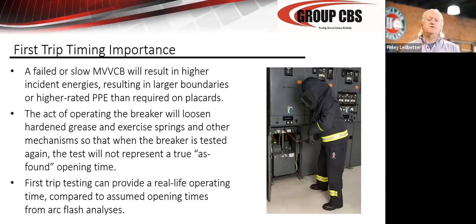Gathering that first trip information is critical to understand whether or not your breaker would have performed correctly and if your maintenance cycle is too long. So basically the hardening of the grease, exercising the springs is all a very important part to get the breaker to operate, react to speed. And I'm going to take a second and give you a little definition and explanation on this. Most timers and most people look at breakers and they talk about parting time. Parting time is when the contacts first part, okay? So when the contacts first part, that is a very useful time for you because you can take that and extrapolate what probably would it operate within time. A timer with a slide wire resistor and also with possibly a rotating resistor can give you velocity, speed, and time to stop. And what that is, parting time is one number.